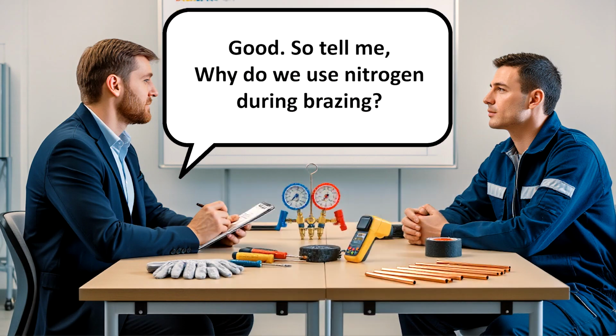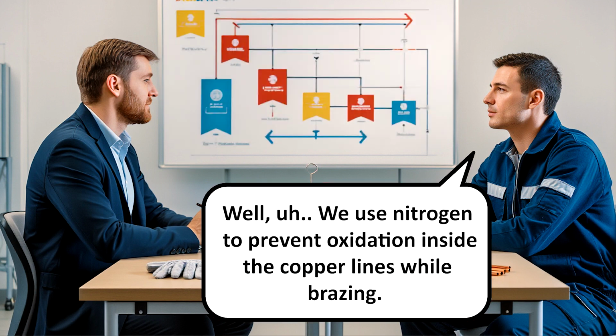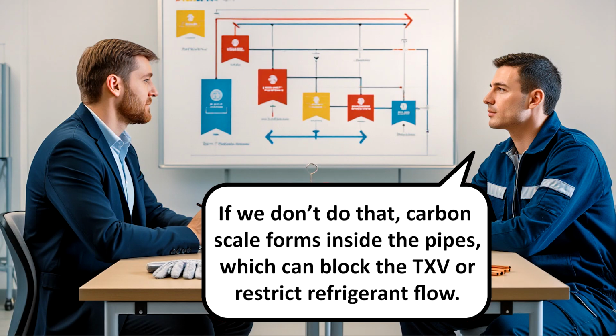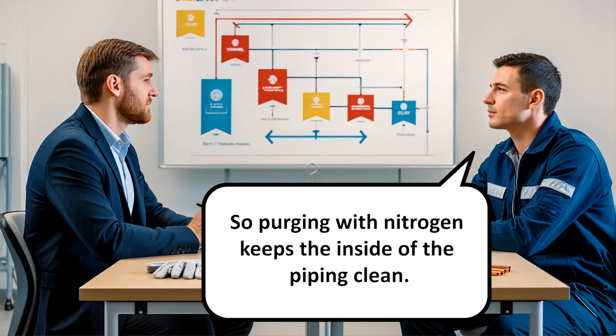Good. So tell me, why do we use nitrogen during brazing? Well, we use nitrogen to prevent oxidation inside the copper lines while brazing. If we don't do that, carbon scale forms inside the pipes, which can block the TXV or restrict refrigerant flow. So, purging with nitrogen keeps the inside of the piping clean.